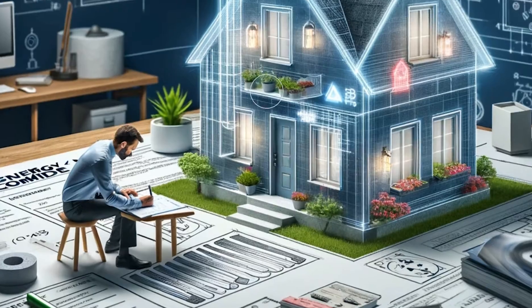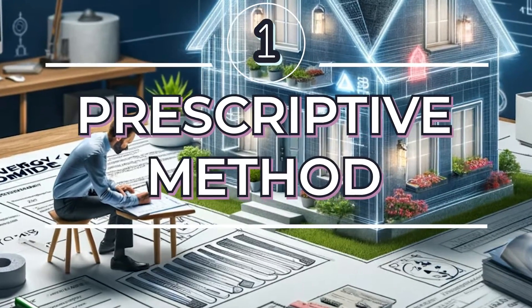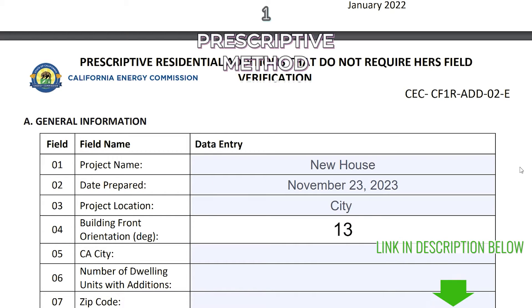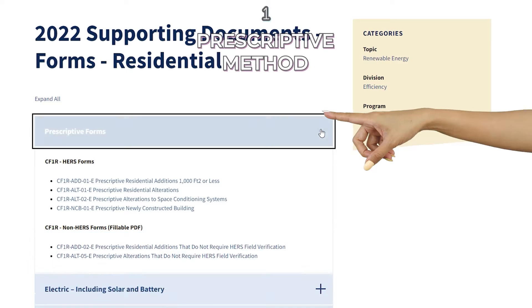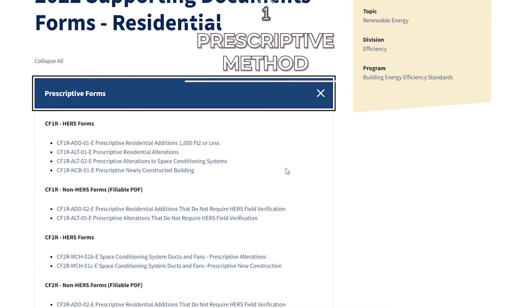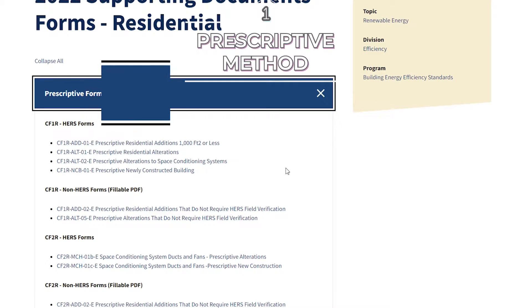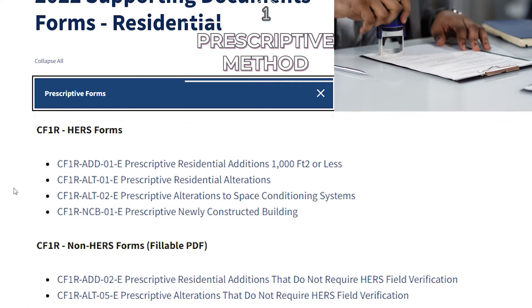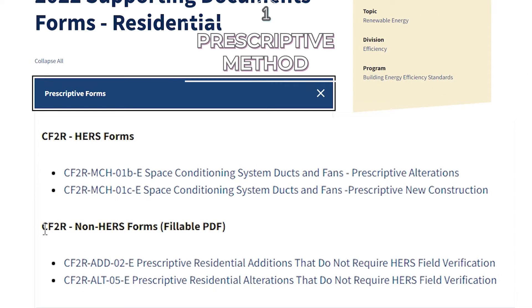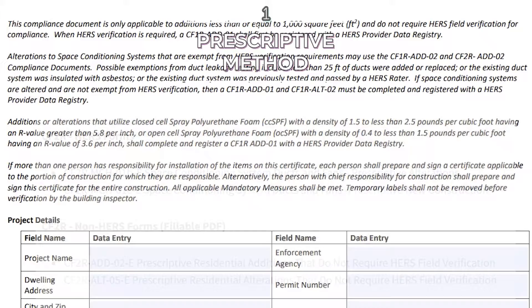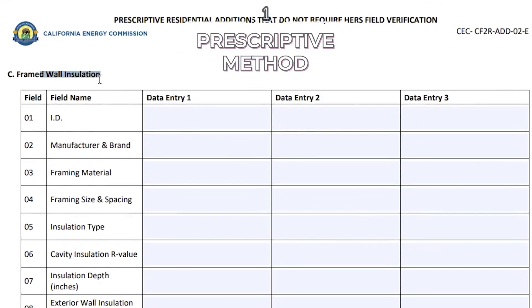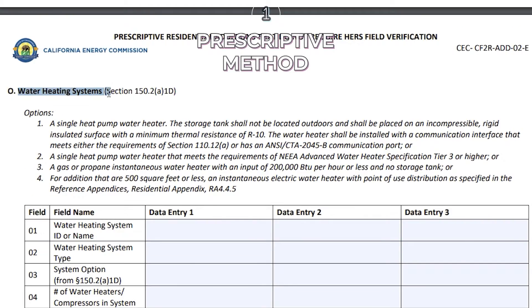How do you get these forms for your project? You have two primary methods. Option one, known as the prescriptive approach, involves using standardized forms provided by the California Energy Commission, available on their website. The link in the video's description will lead you to this site. Under the prescriptive forms tab, you will see two sets of CF1Rs, which are the forms required for permit submittal, and two sets of CF2Rs, which are forms required to be completed by the person installing the building component listed in the energy forms, such as insulation, water heaters, and HVAC system.